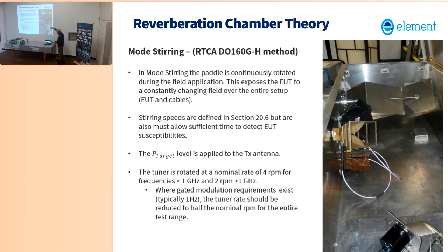Again, your receive antenna is always in there. If you record the values that you get on the receive antenna during the test, then you know for sure that you achieved the field. Whereas when you're running the test in the anechoic chamber, you're just assuming that you're still producing the same field that you got during calibration. In a reverb chamber, you know you do because you're measuring it. The receive antenna's in there the whole time.